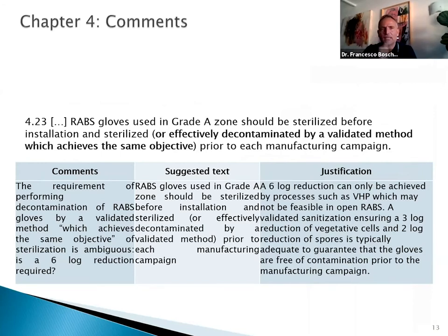Our comment was that the requirement of performing decontamination of RABS gloves by a validated method which achieves the same objective as sterilization is ambiguous. Is a 6 log reduction required? We think this should be clarified, because a 6 log reduction can only be achieved by automated processes like VHP, which may not be feasible in open RABS. So how can we achieve this requirement in open RABS, for example?